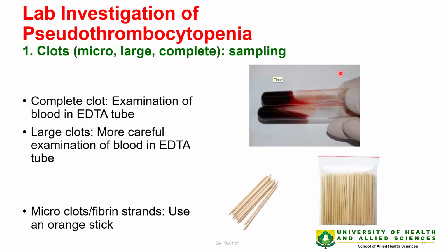Because the danger is that if you don't examine some samples before you run them and there are clots in them, they may obstruct one of the tubings within your hematology analyzer.